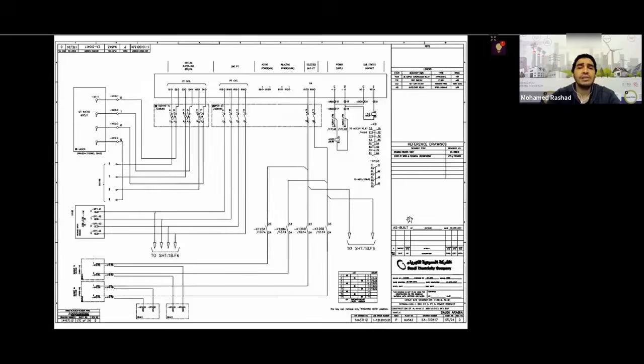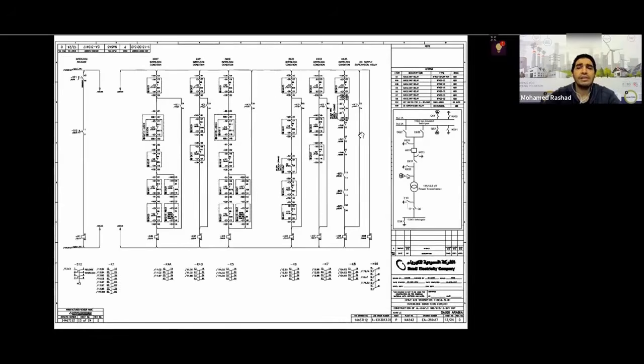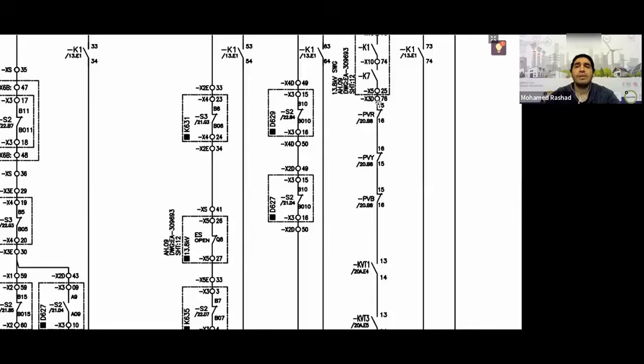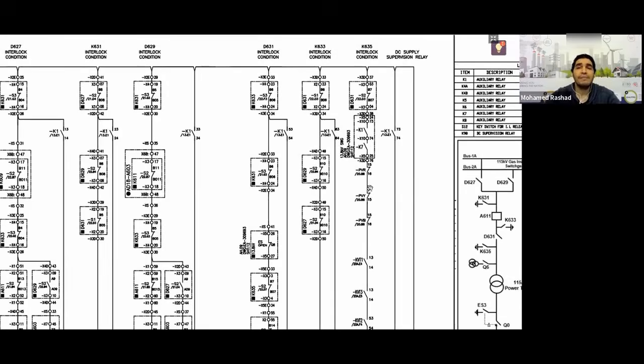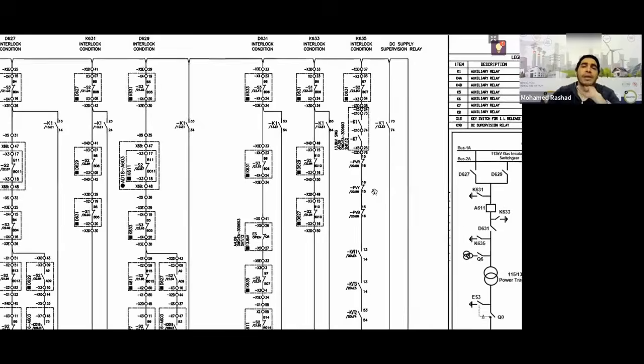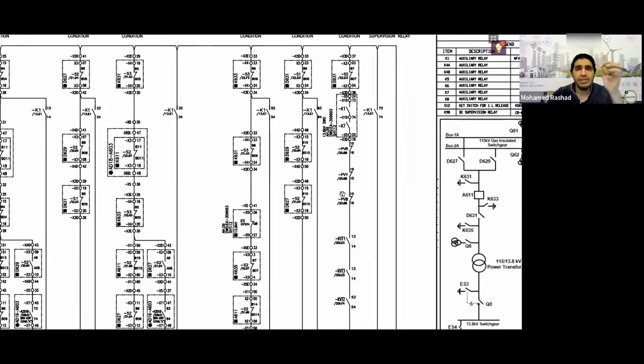And if these 3 are energized, what will happen? If these 3 are energized, you will find here that their 3 contacts are open, which will not allow the earth switch to close. But if there is no voltage, these 3 will drop off and their contacts will return to close, as you can see, allowing the earth switch to close. So how do I know if a line is actually under voltage? For example, well, these 3 auxiliary relays are special auxiliary relays, meaning their drop-off voltage is very low. It reaches 15 or 10 volts as a secondary voltage to ensure that this voltage is indeed very low, almost like a dead voltage. If there is voltage in the middle, there will be a problem.